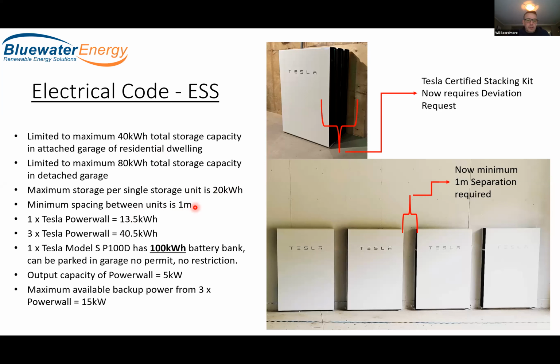So what does this look like? One Tesla Powerwall is 13.5 kilowatt hours of storage. Three Tesla Powerwalls equal 40.5 kilowatt hours of storage. So 40.5 is greater than 40. However, the code does have an allowance of plus or minus 5%, and so the ESA in Ontario, for instance, is allowing us to put up to three Powerwalls in an attached garage.